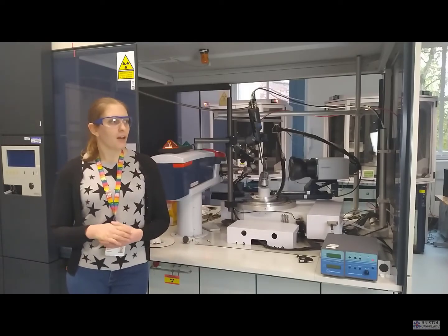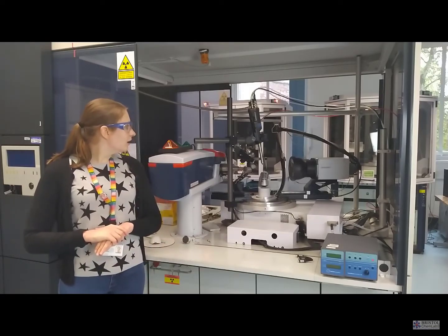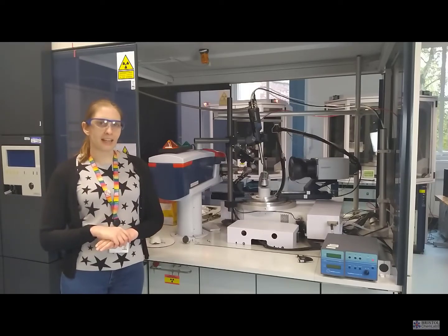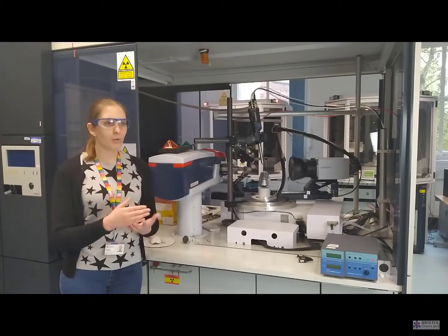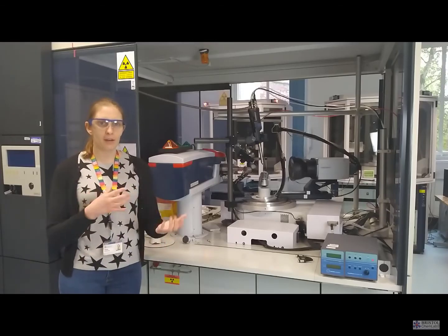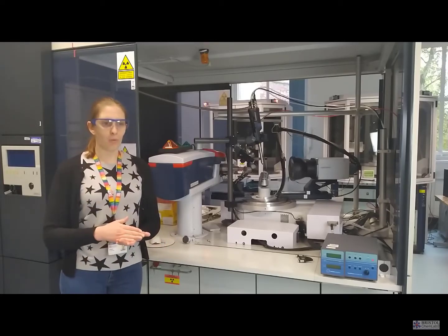That very much depends on the instrument, so that's a bit different for the powder instrument to the single crystal instruments. The most likely bits to break are any of the electronics, because we're using X-rays and they have a lot of health risks. There's a lot of safety features that ensure that you're not exposed to the X-rays, and all those safety features are controlled by microswitches that, when engaged, will let the instrument know that it's safe to run.